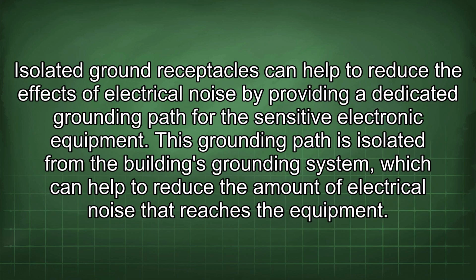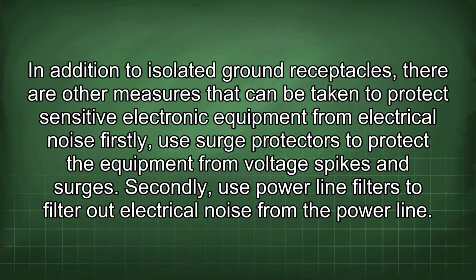Isolated ground receptacles can help to reduce the effects of electrical noise by providing a dedicated grounding path for the sensitive electronic equipment. This grounding path is isolated from the building's grounding system, which can help to reduce the amount of electrical noise that reaches the equipment. In addition to isolated ground receptacles, there are other measures that can be taken to protect sensitive electronic equipment from electrical noise. Firstly, use surge protectors to protect the equipment from voltage spikes and surges.